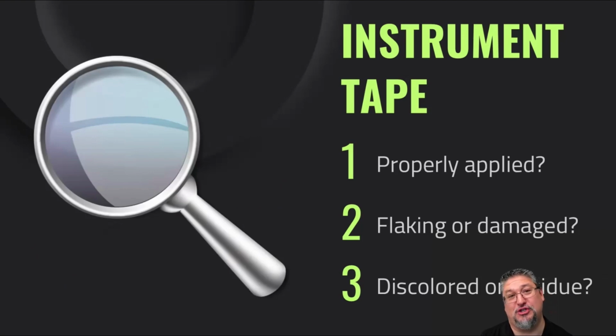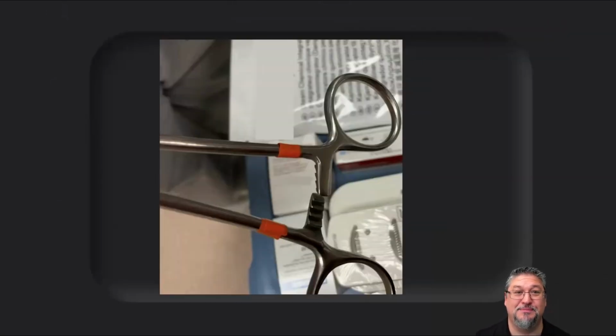If you have tape, make sure it's properly applied. That's a big issue, where they just wrap it 3, 4, 5 times. It should be 1.5 times that it's wrapped around the set or the shank of the instrument. Is it flaking or damaged? Is it discolored, or is there residue? If they see any kind of dark spots on the tape, that's another red flag that there's some kind of residue on it, and it probably should be replaced.